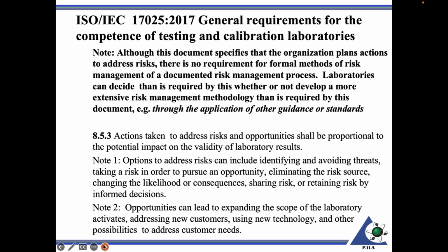Now, one of the things we would look at in that regard is, while this is an expository note, the document specifies that the organization has plans to address risks, there's no requirement for a formal risk management document or application of a documented risk management process. However, it does mean there has to be something that could be examined during the assessment process and evaluation of the package that would indicate the lab has in fact looked at, in light of the availability of PT or interlaboratory comparisons, how they dealt with the risk posed if they didn't participate, in terms of their results in light of the requirements of 17025 and the other documents.